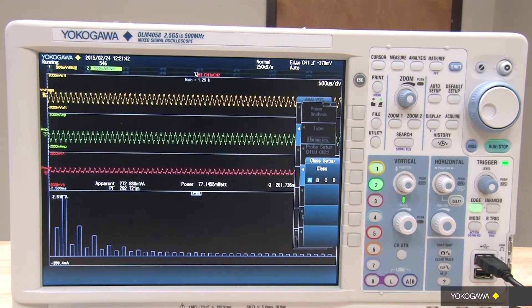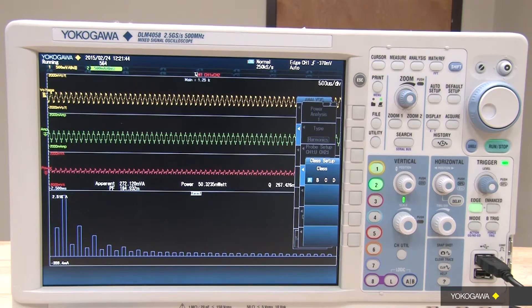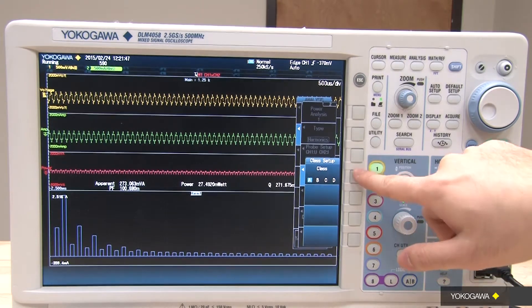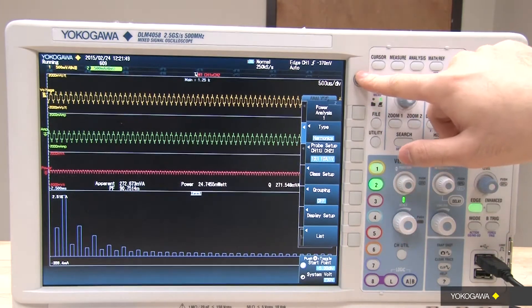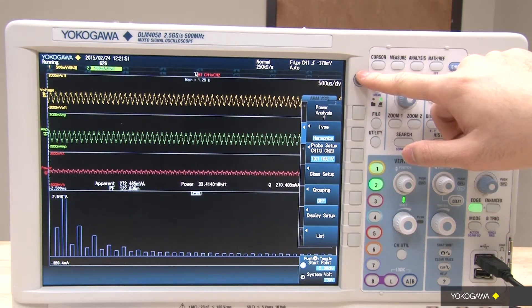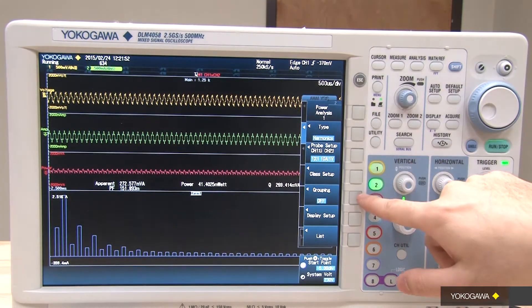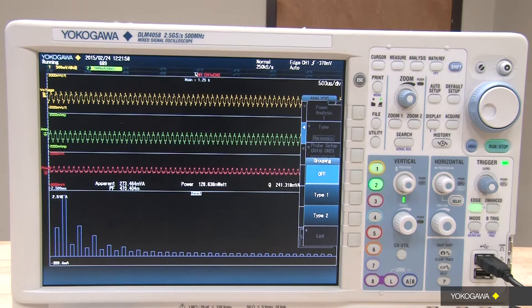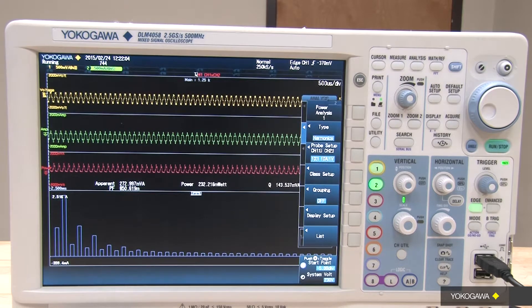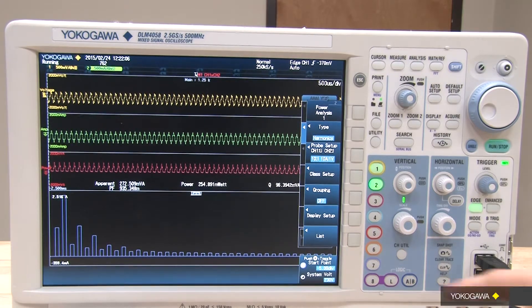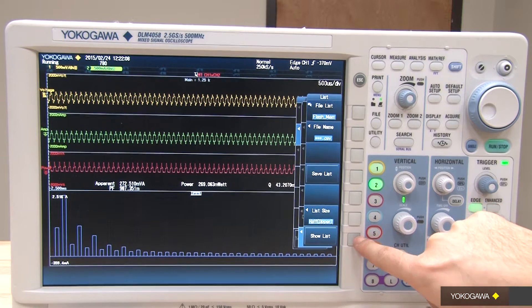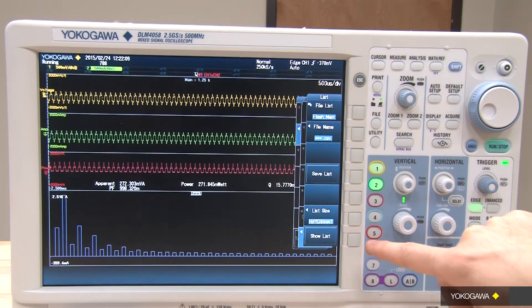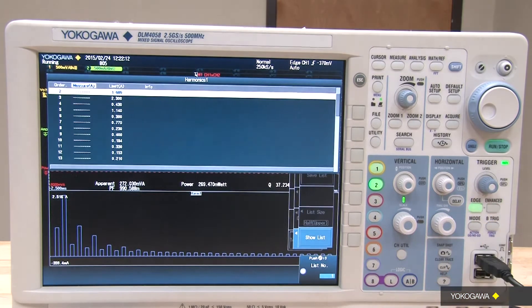There are four classes that this oscilloscope can analyze: Class A, Class B, Class C, and Class D. Once you have selected the correct class, there are two types of grouping for measuring standard harmonics and also measuring inter-harmonics. To view a list of the harmonic measurements, press the list button and show the list to see the measured results.